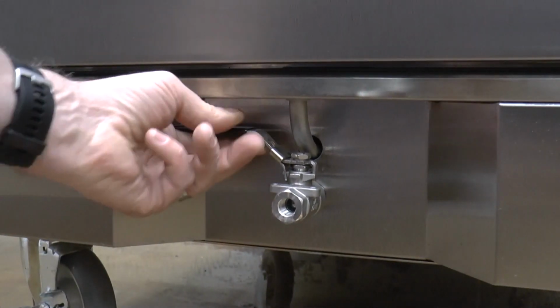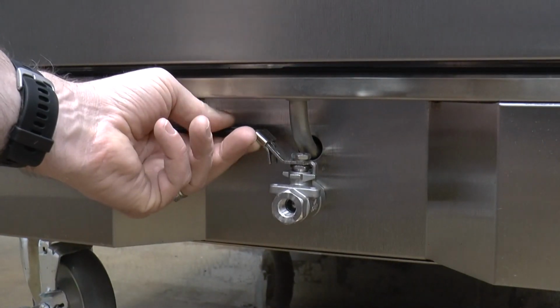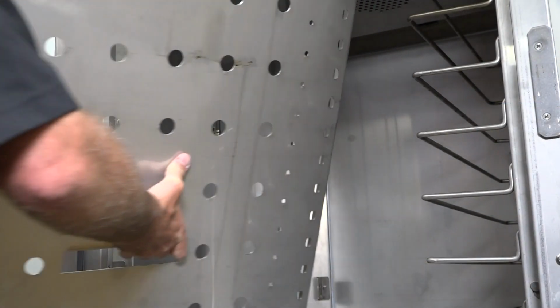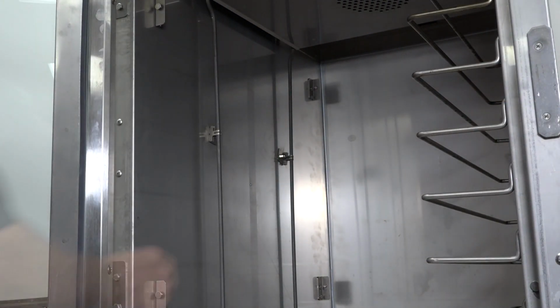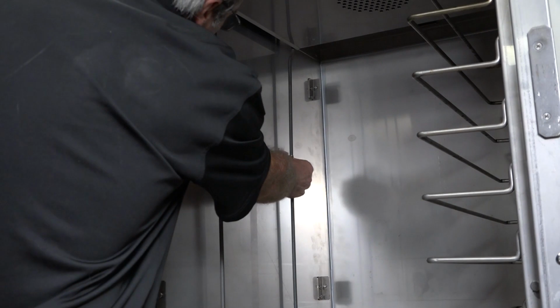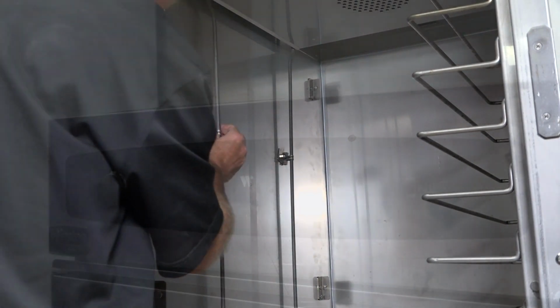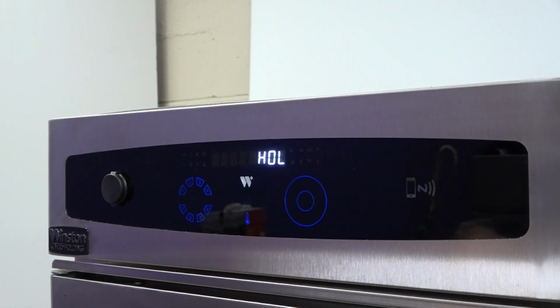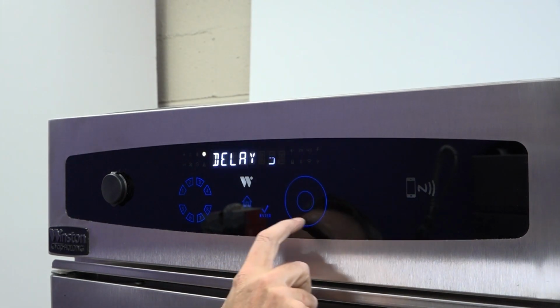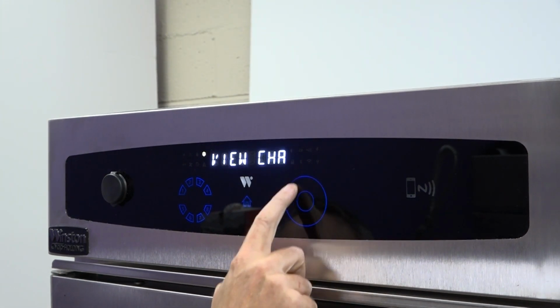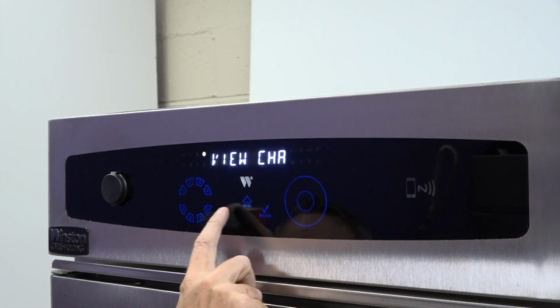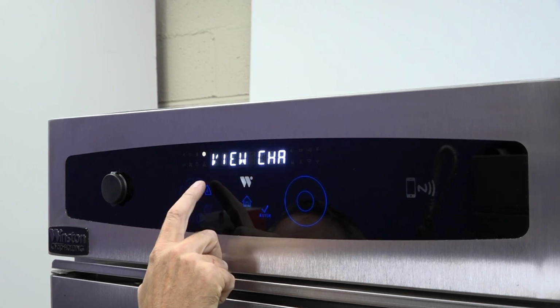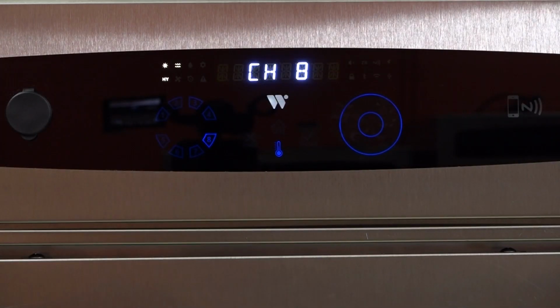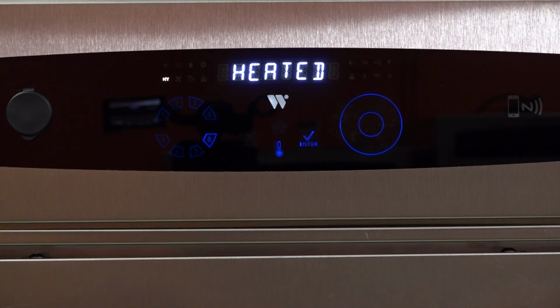Inspect the drain valve to ensure that it is not leaking. Ensure that all heaters are clean and secure in the holding bracket. Inspect the front panel. Ensure that all readouts and touch controls are operating correctly. Set unit to desired temperature set points and ensure that the unit reaches those set points.